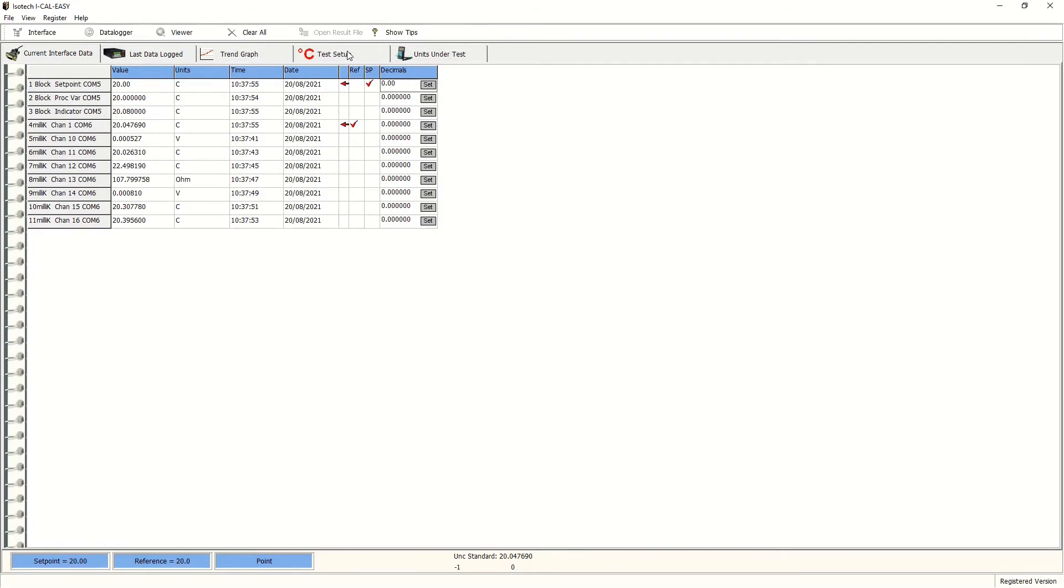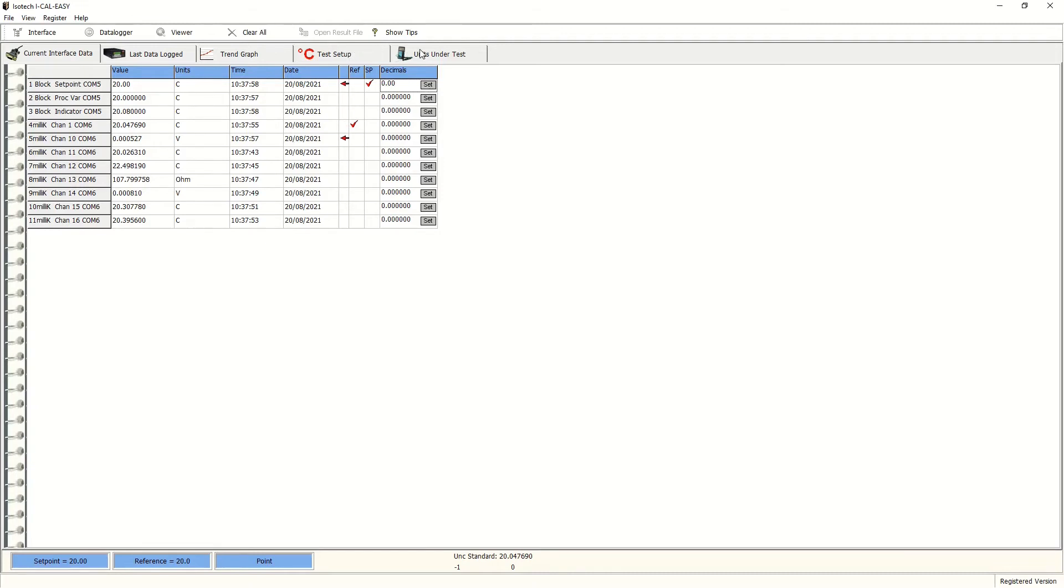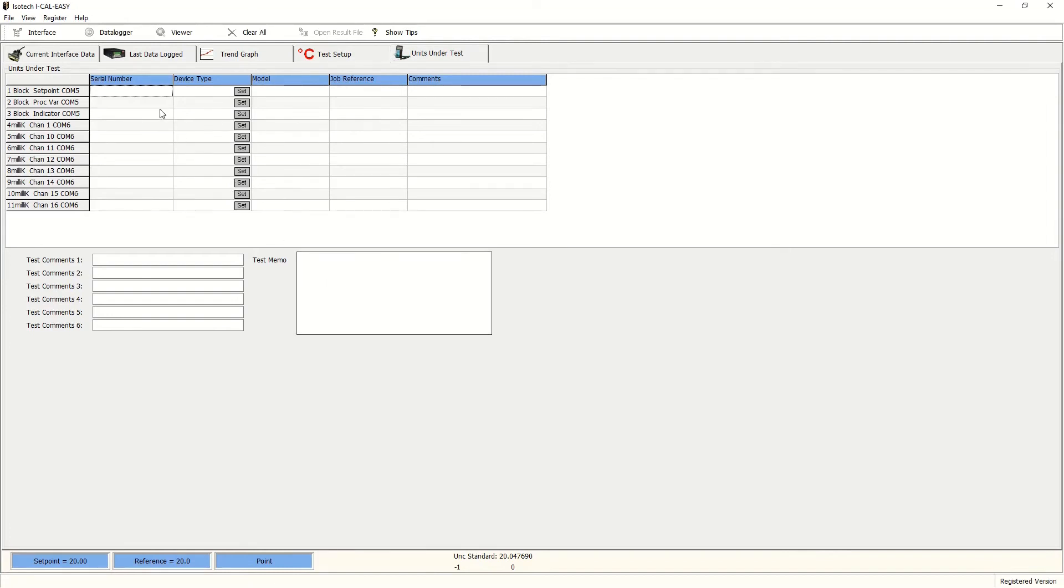Next, we need to configure the actual test points. But before we do that, we can also take the option of labeling each of the positions with serial numbers, engineers, notes about the run, job references and any comments particular to the work order.